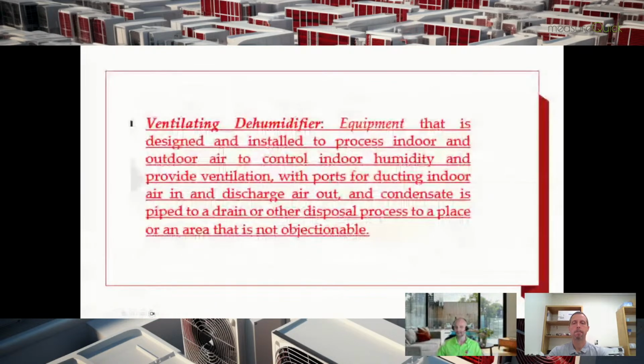So we have ventilating dehumidifier, which is the Santa Fe dehumidifiers are the best example of this. They are the pioneers in the ventilating dehumidifier space. Some of the other dehumidification companies are starting to come out with ventilating dehumidifiers, but these guys wrote the book on it and they do it the best that I've seen so far. And that is a whole home dehumidifier with ports for ducting indoor and outdoor and discharge air that also satisfy the ventilation requirement for the home, the ASHRAE required ventilation requirement for the home.